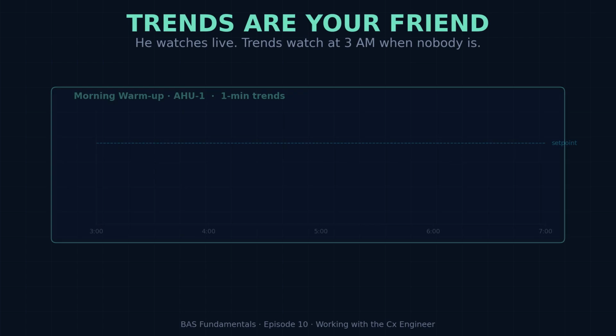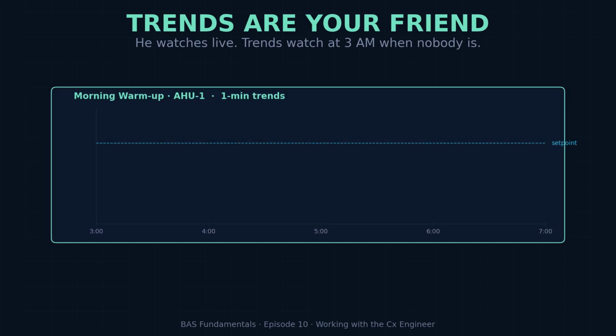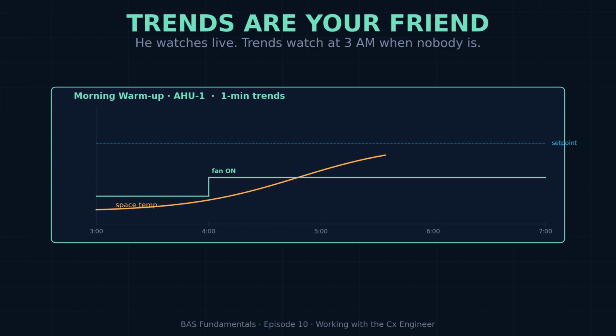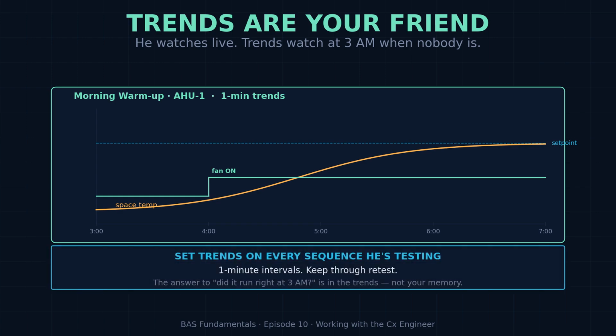One more. Trend logs are your best friend during CX. The agent is watching in real time, but a well-set-up trend lets him go back and see what happened at 3 in the morning when nobody was watching. If the operator asks, "Did the morning warm-up cycle run right?" the answer is in the trends, not in your memory. Set trends on every sequence he's testing at 1-minute intervals, and keep them through retest.